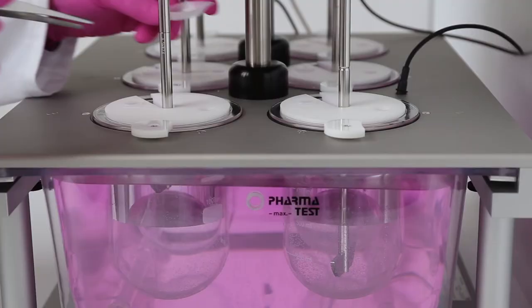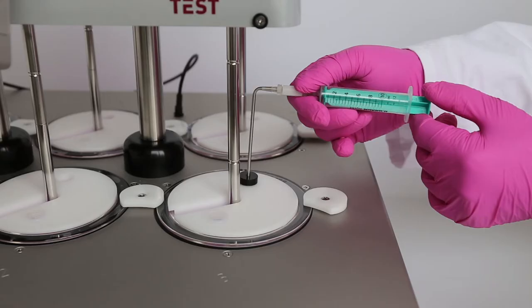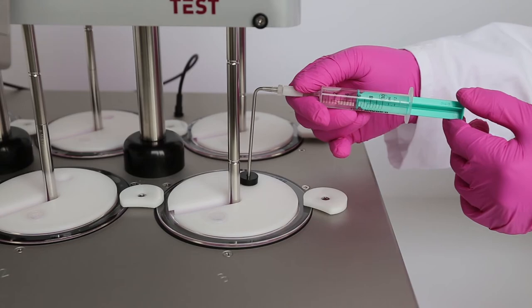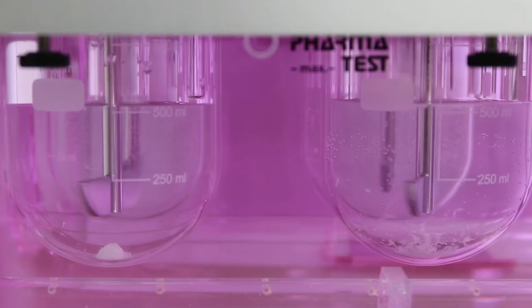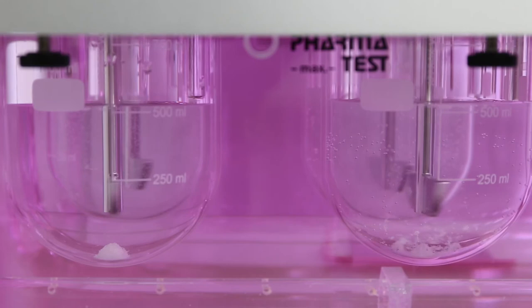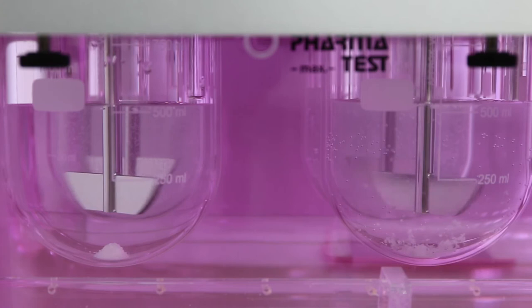The first test shown is the prednisone test with USP apparatus 2, the paddle. Take care that the tablet is carefully released from its packaging to prevent damage. As tablet insertion is done manually, use the staggered start to stay within the sampling time interval — 30 seconds to take all samples after 30 minutes of dissolution. Start the test as soon as the tablet reaches the bottom of the vessel. After 10 minutes of dissolution, the tablet cone shape differs: the left one forms an adequate cone as it dissolves in degassed media, whereas on the right — using non-degassed media — there is no cone and the tablet residues are swirling through the vessel, leading to much higher amounts of prednisone dissolved.